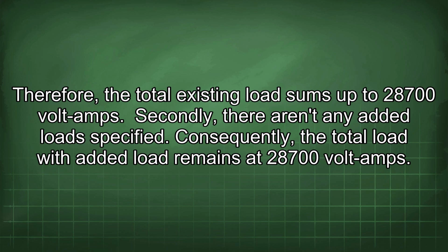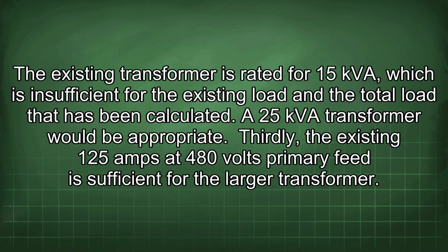28,700 volt amps. Secondly, there aren't any added loads specified. Consequently, the total load with added load remains at 28,700 volt amps. The existing transformer is rated for 15 kVA, which is insufficient for the existing load and the total load that has been calculated. A 25 kVA transformer would be appropriate.